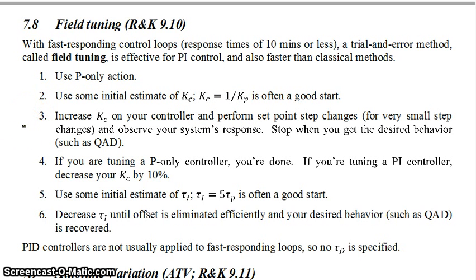You'll use that and perform a set point step change. When you do that, you will continually increase K_C and perform another set point step change until you finally get the desired behavior you want, such as quarter amplitude decay. You will be doing a series of set point step change experiments.